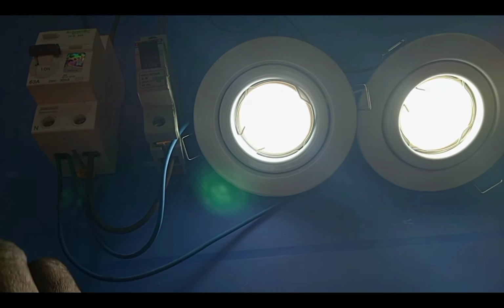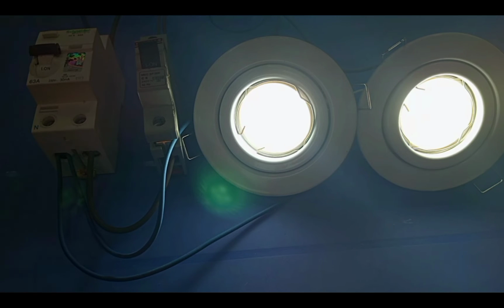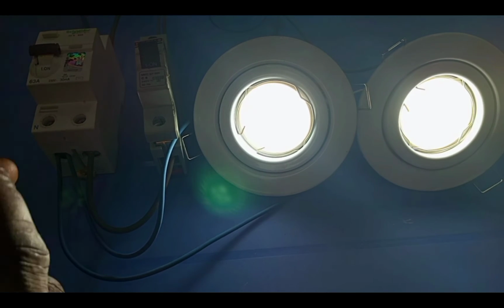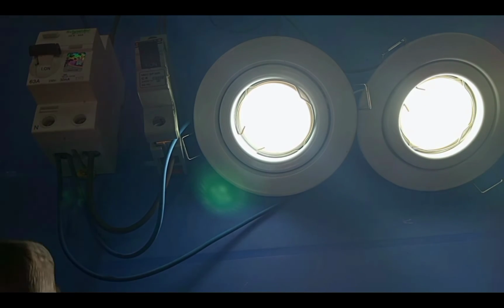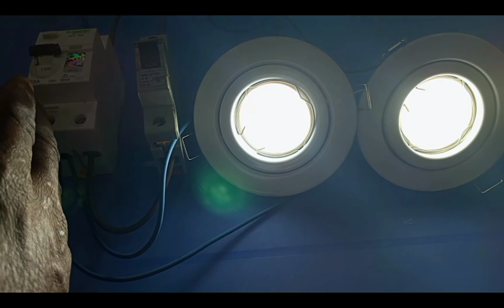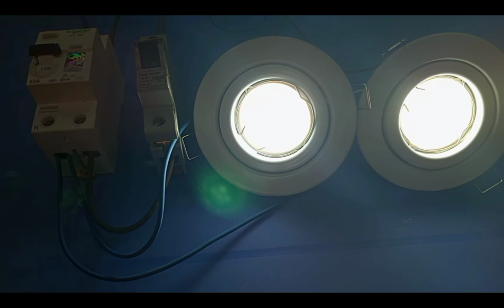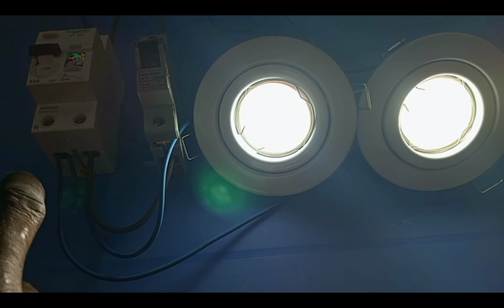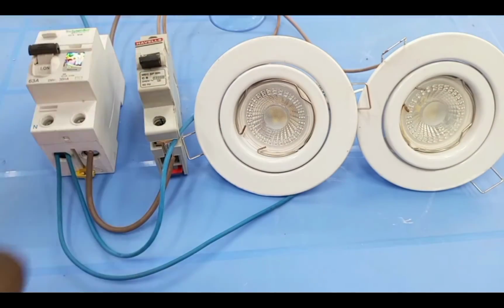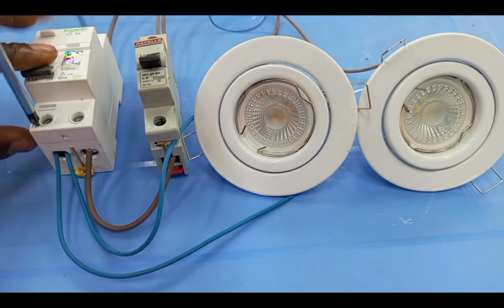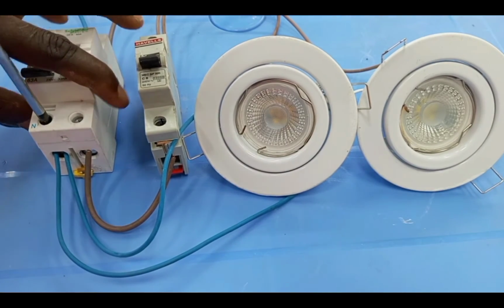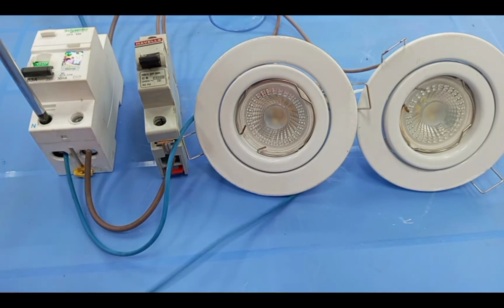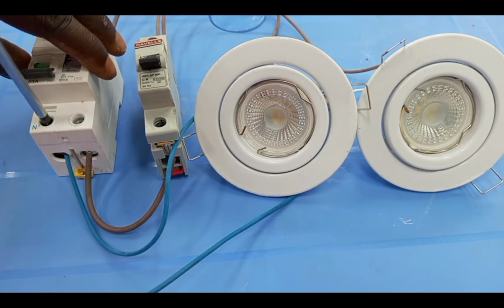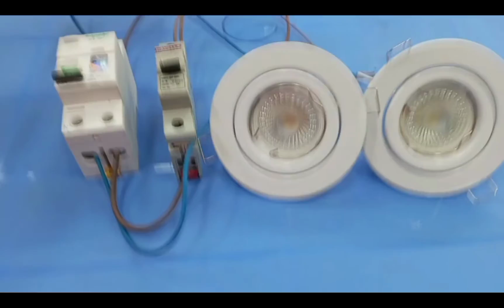And though the rating is 30 milliamp, most of the times the operating value is far below 30 milliamp, sometimes as low as 30% of 30 milliamp current should be able to operate the RCD. All right, so let's look at how that happens. Okay, so this goes off, this goes off, and then I remove the neutral wire I added later.